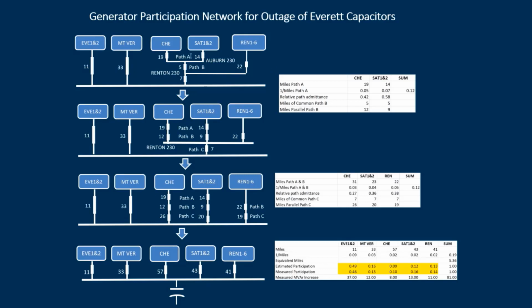We'll call this path here path A and this path here path B. And so we document the miles on path A, and we take the inverse of the miles on path A, and then we take the relative path admittance. In other words, that's the ease of flow on those two paths. And then we take the miles on the common path of 5, and we go through the transformation. We divide the miles of the common path by the relative path admittance, and we get this factor 12 for path B on the Chehalis generator. So that's the 12 here. And the 9 for the path B on the Satsop generators. That's the 9 here.